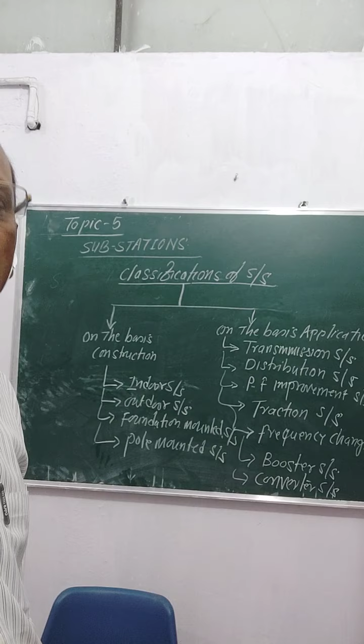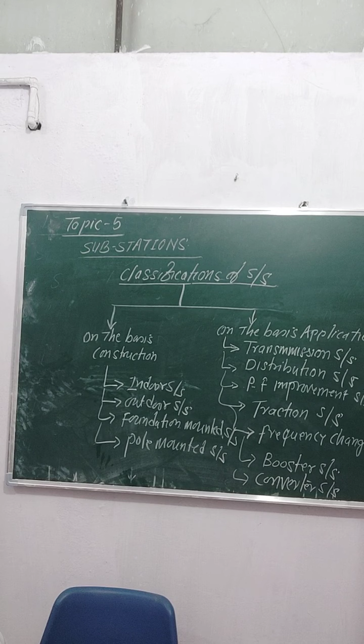But normally in a transmission substation, large transformers are used in MVA capacity. In a distribution substation also transformers are used up to MVA capacity, but maximum up to 15 MVA, and in transmission substation they go for 500 MVA. Power factor improvement substation can be installed on 33 by 11 kV by using capacitor banks. And when you construct a PF improvement substation for extra high voltage, then you have to use a synchronous motor, that is an overexcited synchronous motor running at leading power factor, which feeds negative kVAR into the system to improve the power factor.